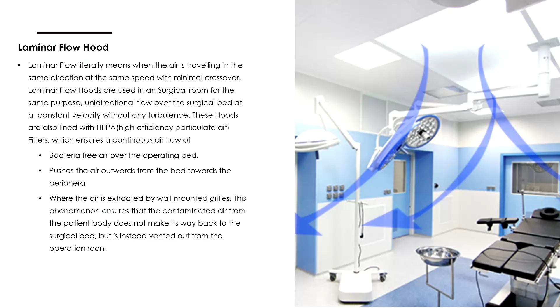ASHRAE justifies two types of operating rooms: one with 100% fresh air, the other with a circulating system using HEPA filters. We did an exercise in Dubai to understand how effective an operation theater with HEPA filters is, and how it looks in terms of energy saving.